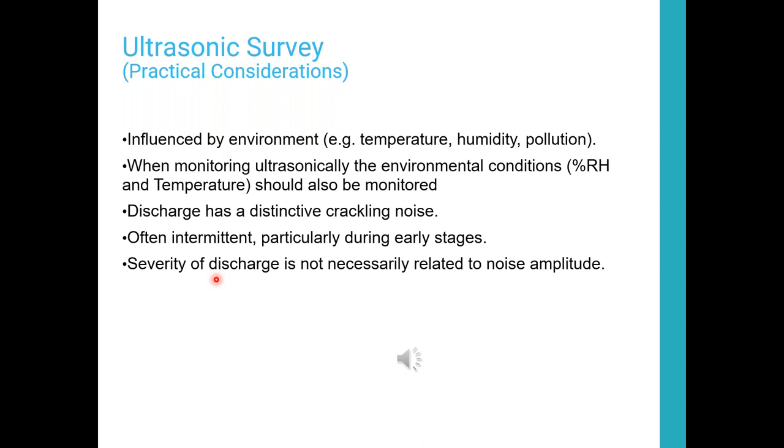So our recommendation was, if you put dehumidifiers in that room and you keep your humidity level down, your partial discharge will stay down. You've got a planned outage coming in a year, and that's when their turnaround was going to happen. If you keep that humidity down and you keep monitoring it, you're probably going to be able to make it to your outage without a failure. Since your policies don't allow you to open the gear up and inspect it to see what the problem is, and it's very active, this is one way you can mitigate it, by controlling your humidity.